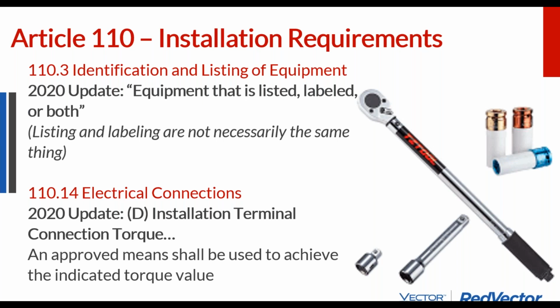Every terminal, every connection on your electrical equipment comes with a torque value in the installation manual: torque this connection to that much. And an electrician can easily say, well, I do this every single day, so I know what the connections should be tightened to. Then their journeyman says, you got it, I know what to do, I'll take over. And then the helper does the actual connection with a power tool and it never gets checked. Where you start to have problems in your electrical connections are loose connections primarily, but there is such a thing as over-torquing and cracking the breaker or the shell of whatever you're trying to mount to. And so, at the bare minimum now, code is mandating the use of a torque wrench for every connection.